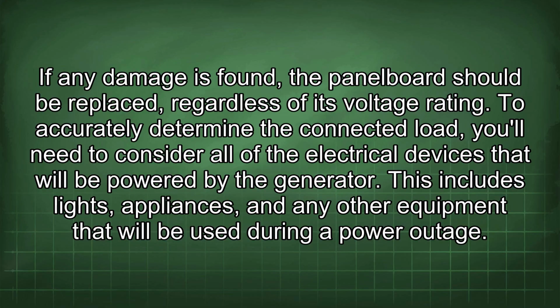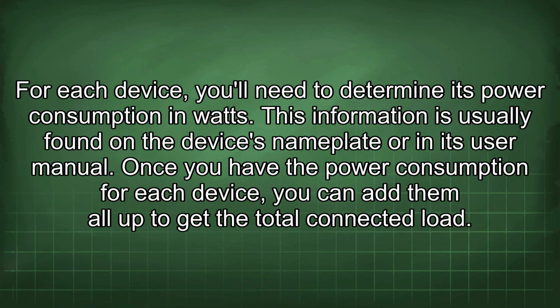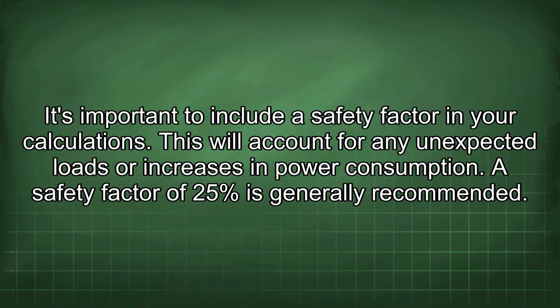To accurately determine the connected load, you'll need to consider all of the electrical devices that will be powered by the generator. This includes lights, appliances, and any other equipment that will be used during a power outage. For each device, you'll need to determine its power consumption in watts. This information is usually found on the device's nameplate or in its user manual. Once you have the power consumption for each device, you can add them all up to get the total connected load. It's important to include a safety factor in your calculations. This will account for any unexpected loads or increases in power consumption. A safety factor of 25% is generally recommended.